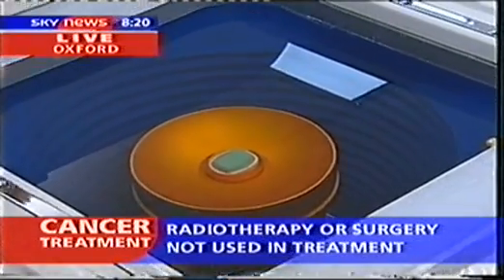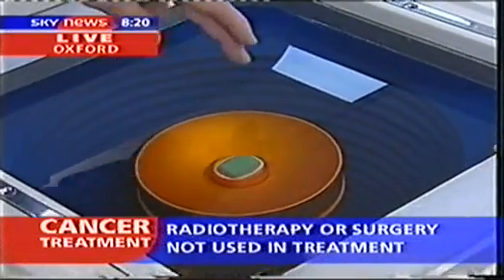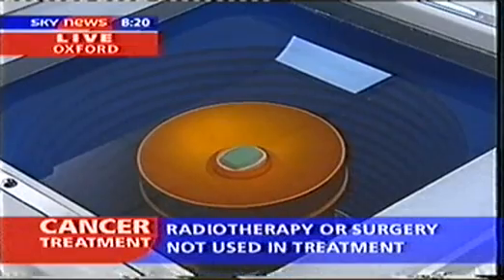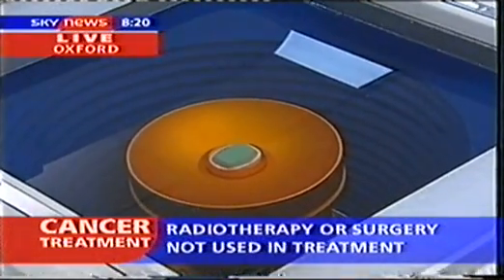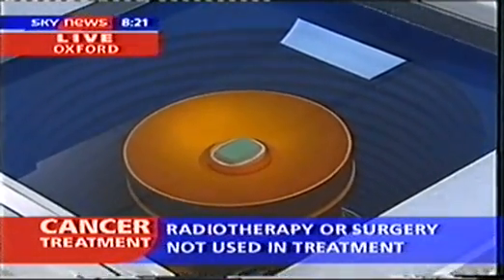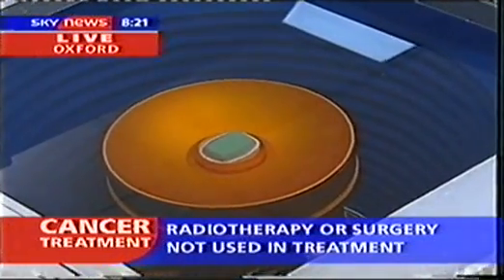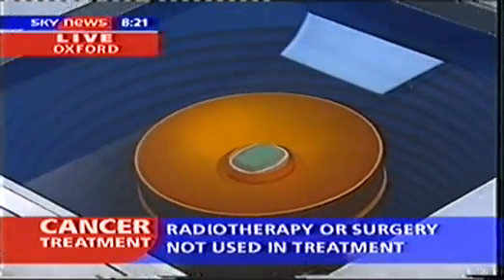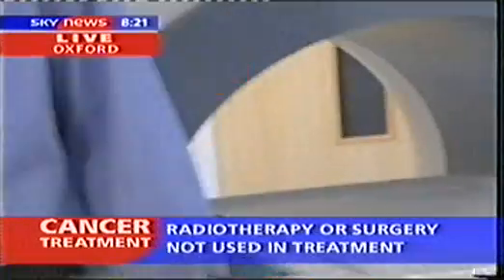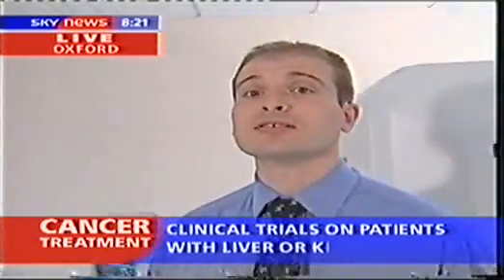The difference with this device is that, as you can see around the outside, there is a much larger device, and this operates using higher intensity ultrasound, which carries a much higher energy level than the ultrasound beam. That ultrasound is brought to a tight focus, and at that focus is where the tissue is damaged.